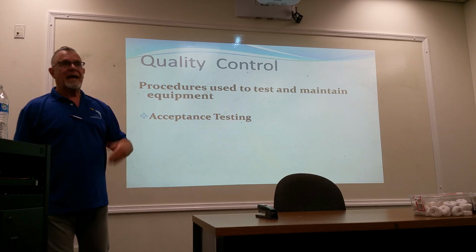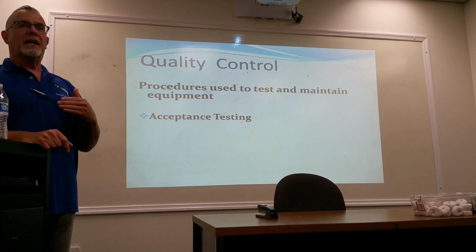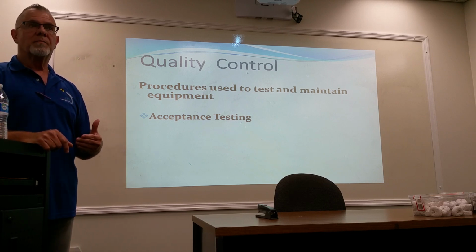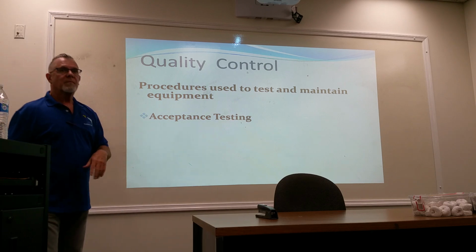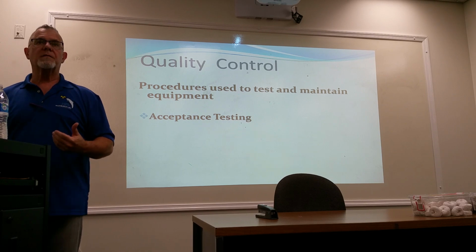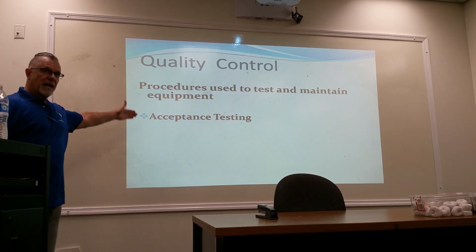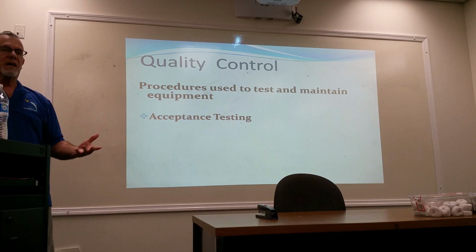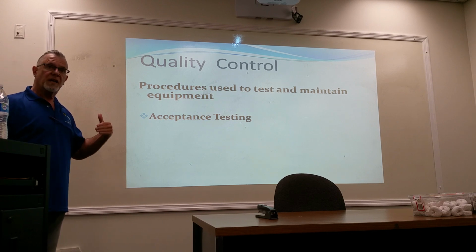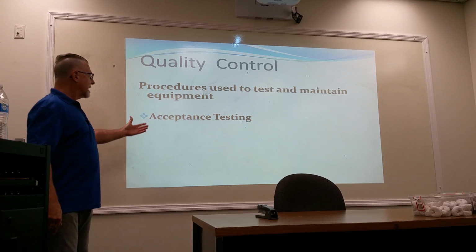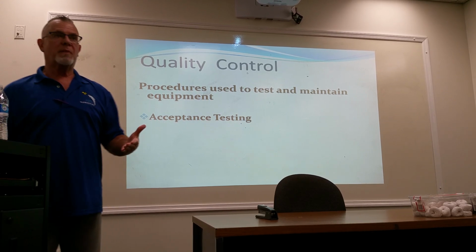requires that every piece of X-ray equipment coming into an accredited facility, hospital, has to go through an acceptance test by an approved medical radiation physicist. Now, when I was working, that's some of what I used to do. So you had a set group of tests you had to do. You compared that with what the manufacturer specifications had. Okay? And you either passed the equipment or you didn't.